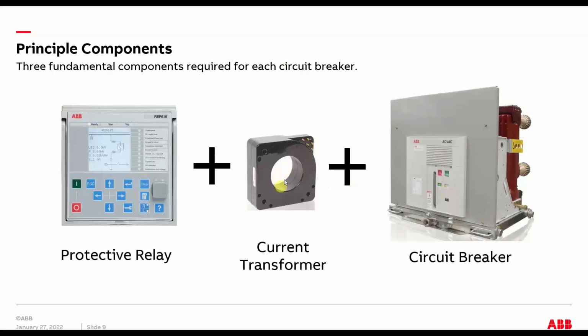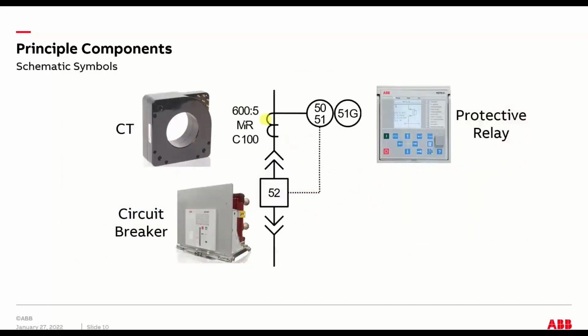Even the current transformer, people with a sharp eye will realize that this one is a 600 volt class CT, but it's used in 15 kV switchgear because it goes around insulating bushings. So this is the actual class of CT that we would use in our medium voltage switchgear lineups. Here's a slide showing the physical device in relationship to some of the symbols used. These two circles show an instantaneous overcurrent and a time overcurrent ground. All these elements are part of this single box, plus a whole slew of additional stuff.